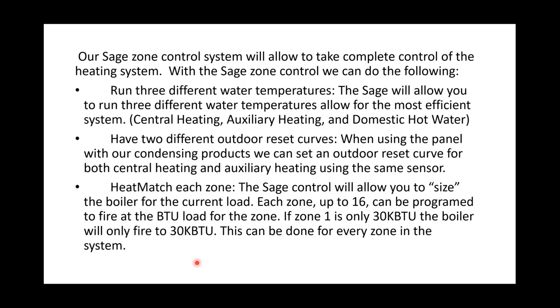Heat matching allows us to size for the proper load, to cut down on short cycling. In many cases, by using the Sage panel, I can pull a buffer tank out of the picture. Velocity also does now offer buffer tanks. We have a 30, a 40, I believe a 70-gallon buffer tank. Don't quote me on the last one. I know the two smaller ones. But it's a 75, there we go. See, that's why the salesman's on here, not just the tech guy.